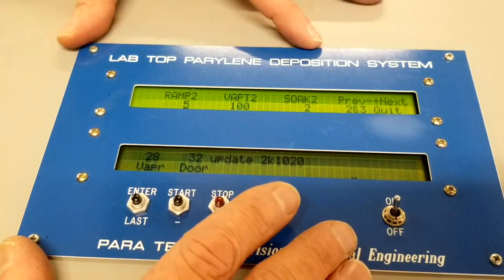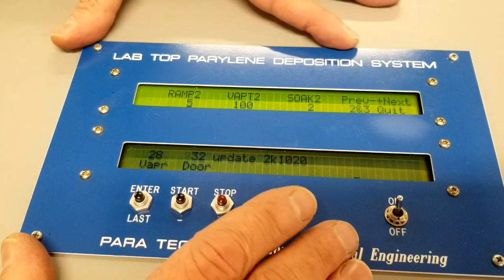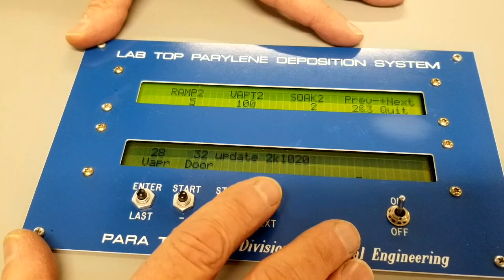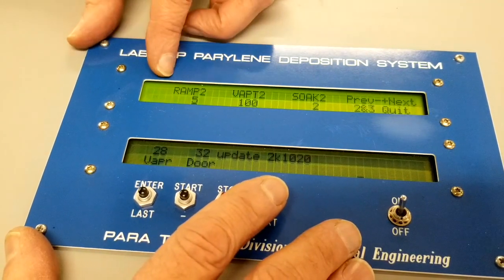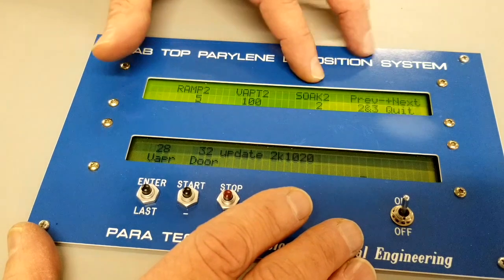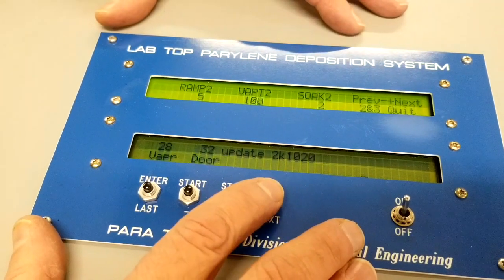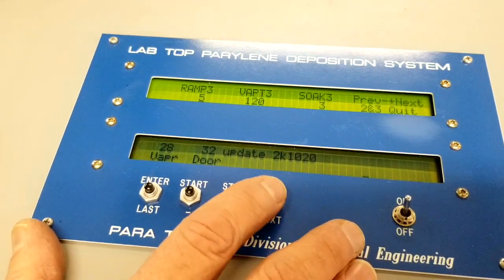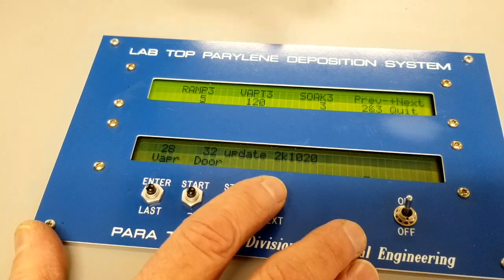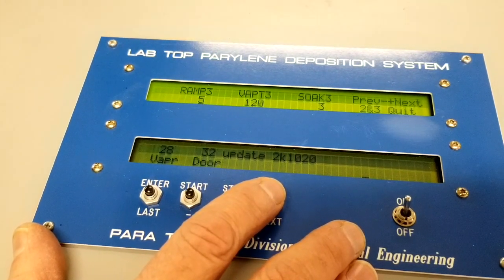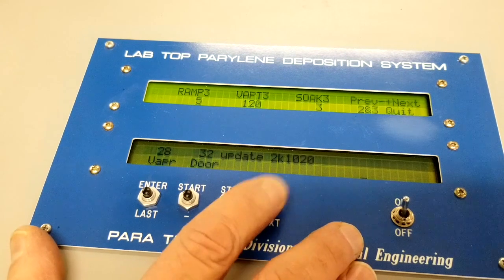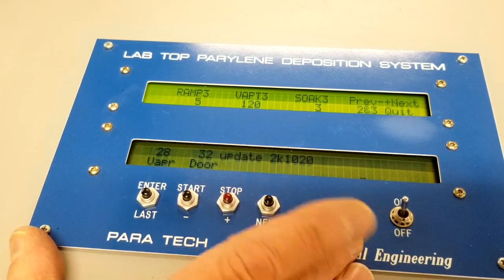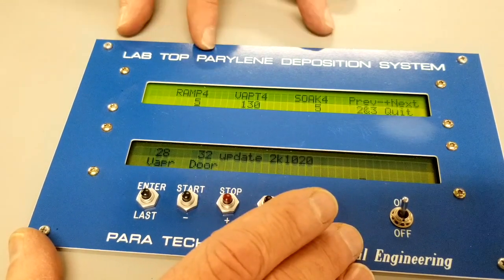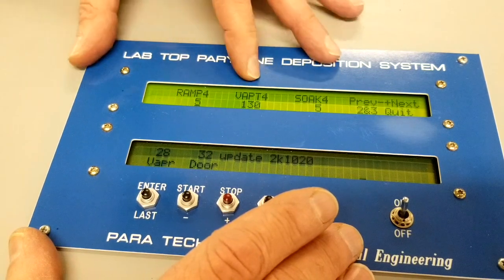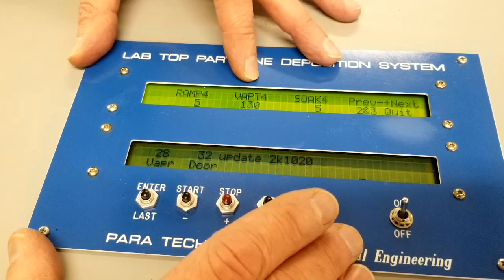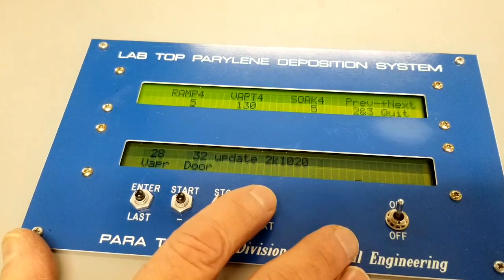And again, this is just a quick program just to show that the temperatures will rise and that the system is working. Again, this is a 5-minute ramp to 100 in the vaporizer, 2-minute soak. And we'll step through that. Ramp 3 up to 120. 5-minute ramp, 3-minute soak. Just by hitting the next button, we're stepping through it. This is your ramp 4, which is your final ramp. We're going to ramp to 130, 5 minutes and soak for 5 minutes.